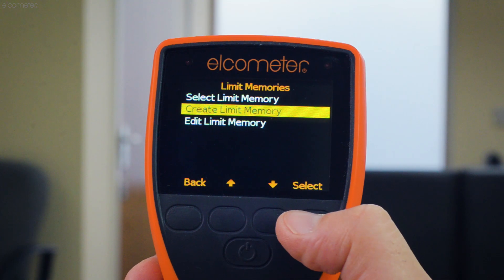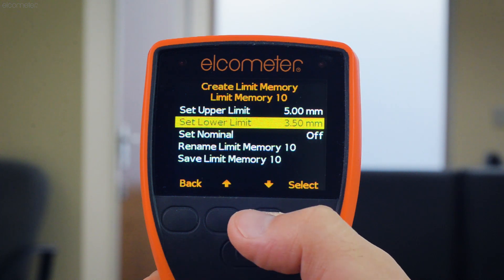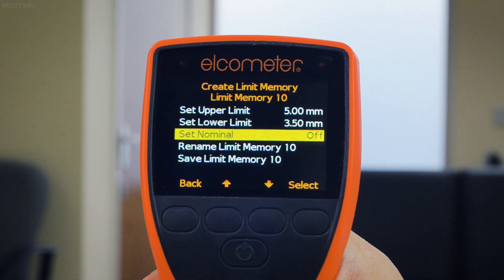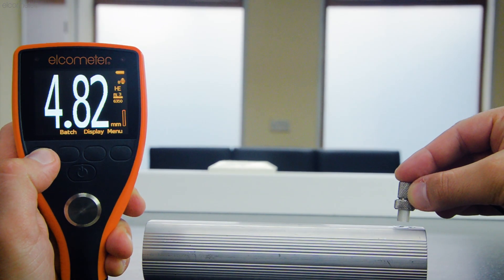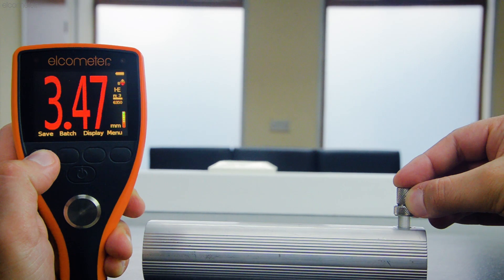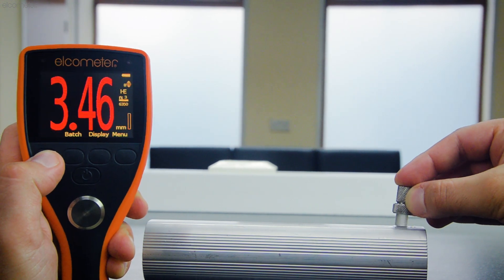With limit memories, the Elcometer PTG-8 allows you to set high and low limits, as well as the previously mentioned nominal target thickness. Once defined, whenever a reading exceeds these limits, the gauge gives you an audio and visual warning, clearly highlighting any problem areas.